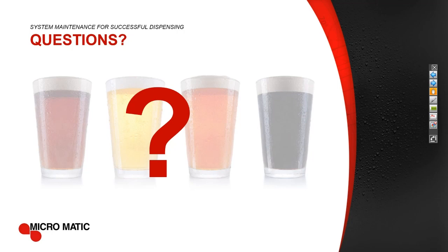Yes, good catch. Lots of cleaning related questions. This is a great one from Mike. He asked, does CO2 degrade the cleaning process? And does water quality matter, hard water versus soft water? So CO2, I do not know to the 100% degree, but CO2 does degrade or makes caustic weaker. Let me put it that way. Is it enough to change it? I don't know that we know that, or at least I don't, but it does make it weaker. My chemical will never be stronger than the first pass through. So if I'm pushing beer out with my caustic, then the beer has CO2 in it. It will make it weaker.